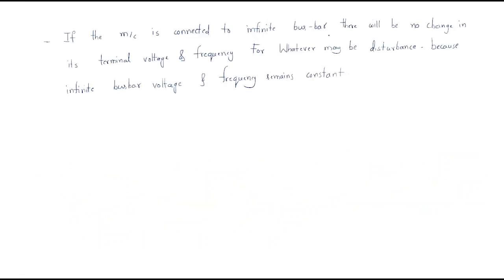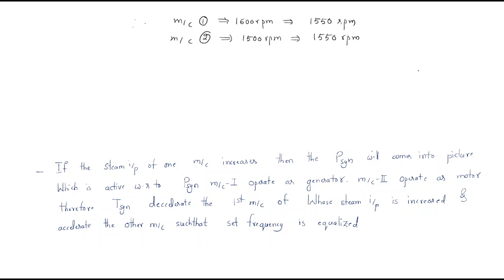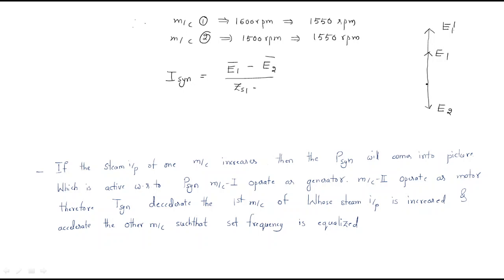Initially the EMFs are E1 and E2. The steam input increase causes E1 to rise to E1-dash. The synchronizing current is then given by: I_sync = (E1 − E2) / (Zs1 + Zs2). This synchronizing current is generated by the interaction of the two machines.